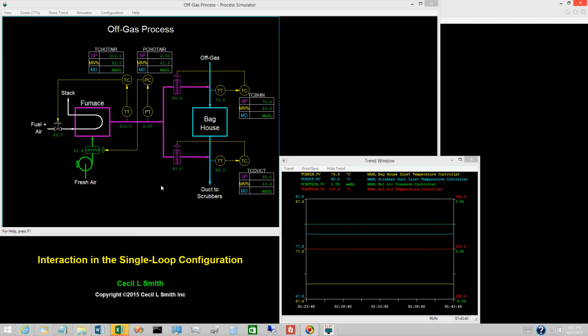Our focus is on the scrubber duct inlet temperature controller. The measured variable is the scrubber duct inlet temperature. The controller output is the opening of the hot air damper to scrubber duct inlet. The test will obtain the response of the measured variable to an increase of 5% in the controller output. Initially, the process is lined out at its normal operating conditions. All controllers are on manual.